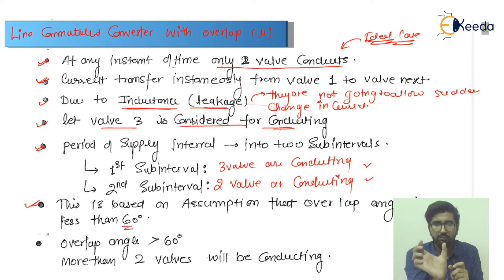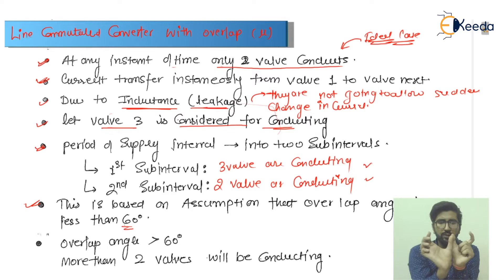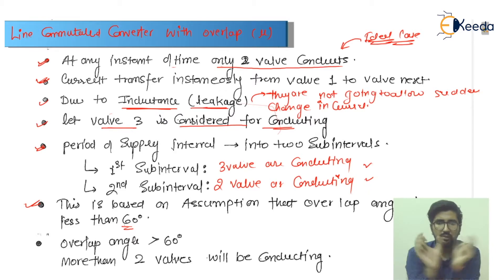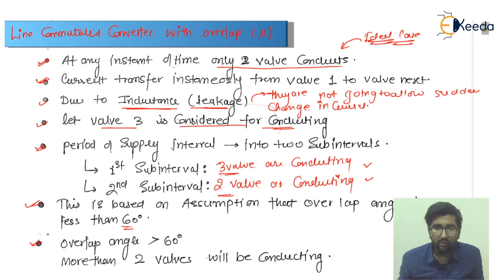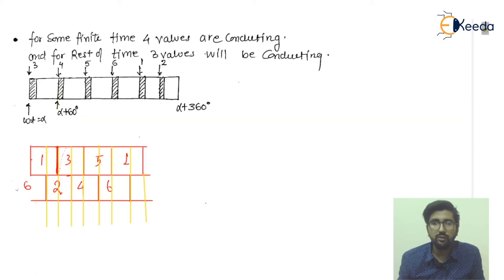To understand overlapping: suppose valve one is conducting for some time — ideally valve three should only start after valve one completes, but due to inductance valve one operates longer than intended, so valve three starts before valve one finishes. This overlap period exists when the overlap angle is less than 60 degrees. When the overlap angle is greater than 60 degrees, more than two valves will be conducting.